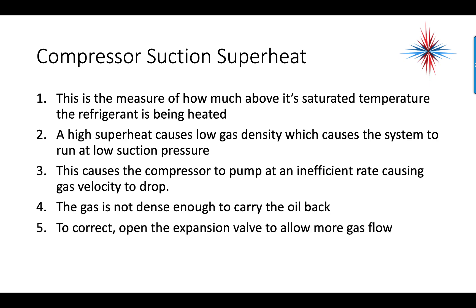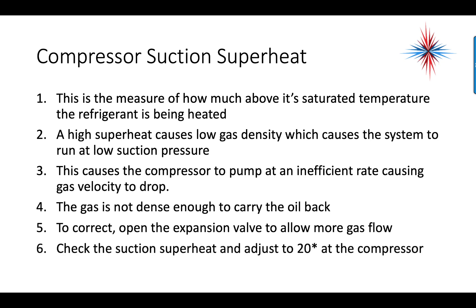To correct high superheat, open the expansion valve if available to allow more gas to flow back — in other words, lower your superheat. If your system is undercharged, charge it. To check the suction superheat, adjust to 20 degrees at the compressor.